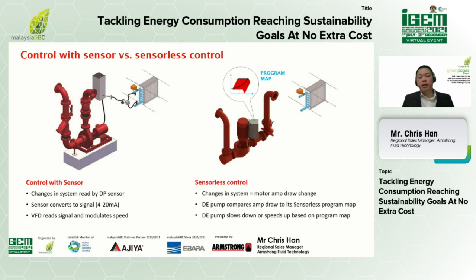Now let's take a look at what sensorless technology is about and what it can do, on the right-hand side. So with sensorless pump control, the changes in the system are detected by the sensorless pump control as the motor amp draw changes. As the control valve opens and closes, it detects it as a change in motor amp draw.